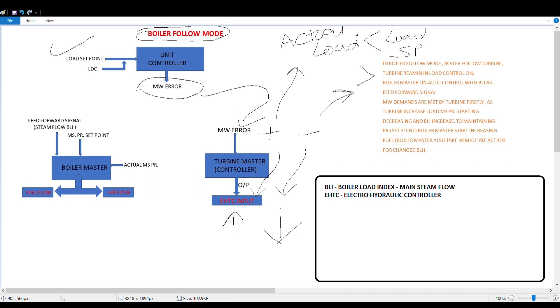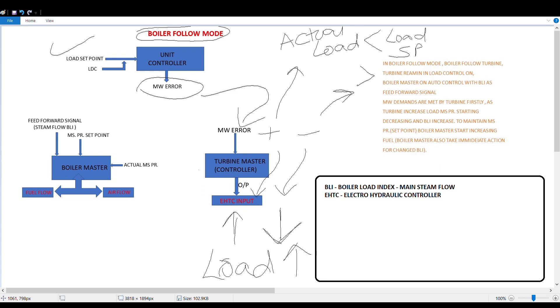In this process, the boiler is not touched initially — no signal goes to the Boiler Master's feed-forward input. The boiler maintains the state it was in before the load set point input was received. Assuming we change the load set point at time t, the boiler master maintains its state from t-1. The EHTC input is then increased or decreased based on the megawatt error, and the actual load will increase toward the desired load.